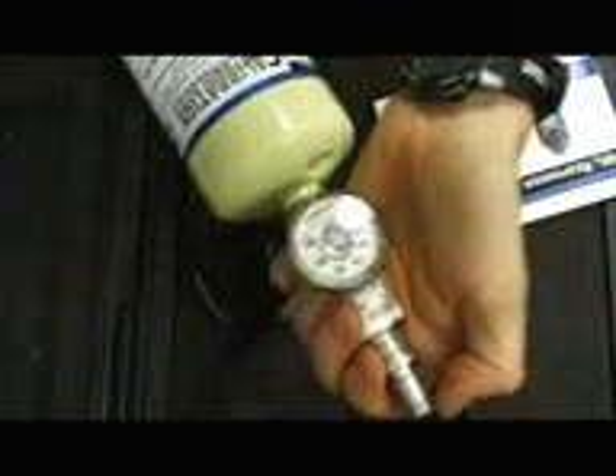The best way to put these on, I found, is to hold the demand flow regulator in place and twist the bottle on, as opposed to the other way around. That way your cord's not whipping around on you. As you can see from our gauge here, we have between 250 and 300 pounds per square inch. Again, I'm looking at my bottle to make sure which gas I have on here. In this case, it's a 50% LEL, and my expiration date is August of 2013, so that should be fine. I want to make sure that that's closed and not open. When I go to calibrate the monitor, I will pop that open.